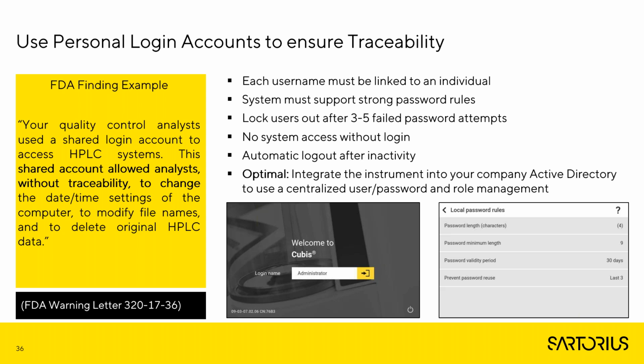It should be a personal account, and the system needs to include functionality to stop other operators from using it. Let's say complex passwords, account locking after an excessive number of failed login attempts, or even automated logout after inactivity are examples of this. A central administration of the user accounts is highly important, especially with a crucial laboratory tool like a balance. The best option would be to directly integrate the instrument into an Active Directory or a centralized user management server without using any intermediary software.